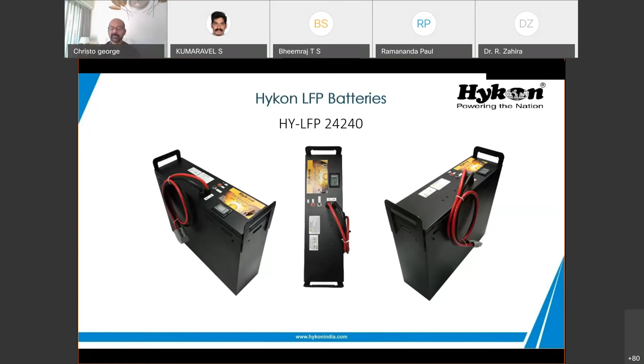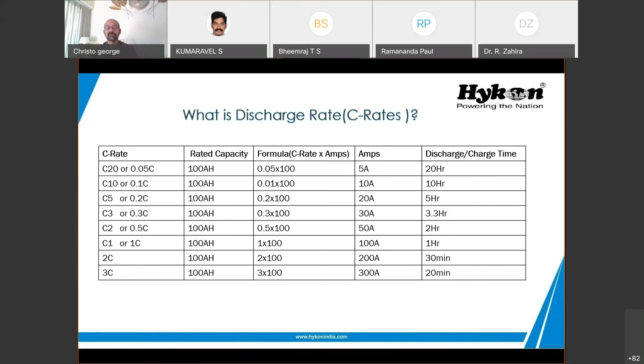Another point is discharge, called the C rate or current rate of a battery—different batteries have different discharge rates. A C20 lead acid battery, available in the market for inverters, can be discharged fully in 20 hours. A C10 tubular battery, mainly for UPS, can discharge that power in 10 hours. But when you go to 2C, it means it can discharge 2 times the battery capacity—so a 100 Ah battery can discharge at 200 amperes. With lead acid there's a limitation, but with lithium ion, high discharge is possible, which is why lithium is mainly used for electric vehicle systems.